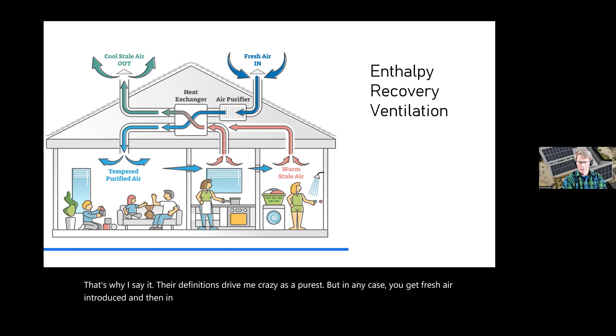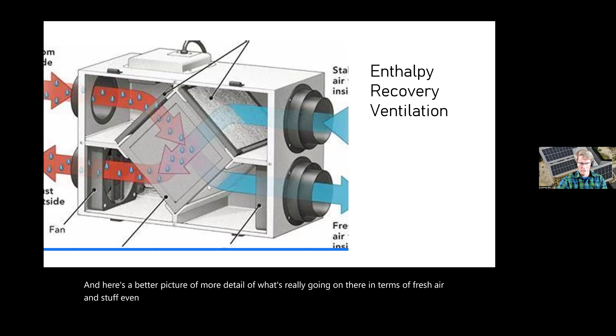The difference is ERVs deal with latent heat and have a porous membrane where moisture can pass back and forth. Some people call these energy recovery units, and the other variety heat recovery units. Their definitions drive me crazy as a purist. In any case, fresh air is introduced, and in bathrooms and kitchens the exhaust goes out the other side. Here's a more detailed picture of what's really going on, even though it doesn't fully show the moisture transferred through the porous membrane.